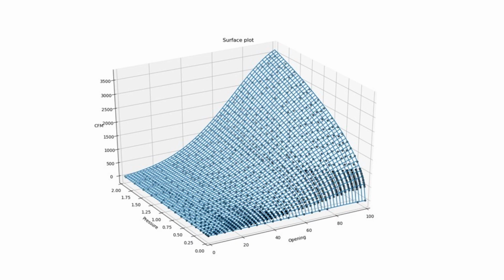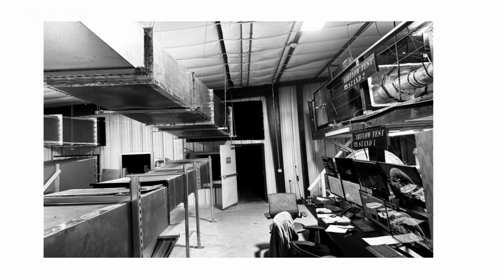The three axes include airflow CFM, pressure and damper position opening. The SAV ships with a 700-point factory commissioning report, validated from 0.03 to 2 inches of water gauge on calibrated airflow stands. Units are certified per ASHRAE 195, including the controller, transducer, and SAV terminal unit. Factory-witnessed performance testing is encouraged.